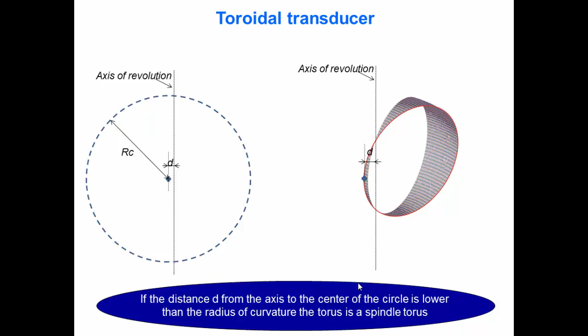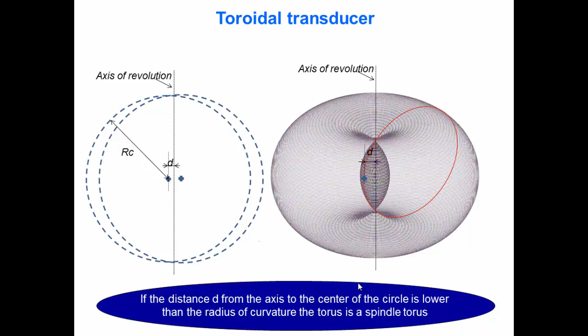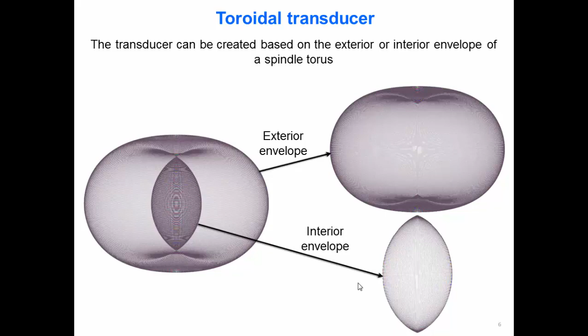There is one particular case. If this distance d is lower than the radius of the circle, the torus is called a spindle torus. And as you can see, there are two envelopes inside this geometrical figure. And since there are two envelopes, we can create two different shapes of a HIFU transducer, one using the exterior envelope or one using the interior envelope of this spindle torus. For that particular case, we chose to use the interior envelope of the spindle torus to develop our toroidal HIFU transducer.